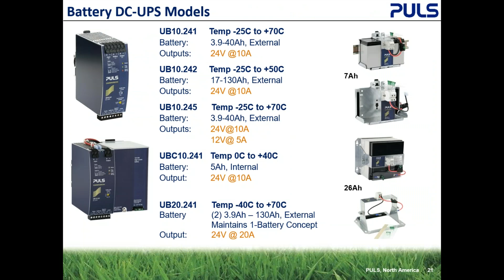I'm showing this because a lot of people now are getting into backup systems. I think they're starting to see the benefit of a DC backup. So we make DC backup systems, and I specify DC because everything Puls does is a DC output, we don't have any AC outputs. So if somebody says, I have a backup, but it's AC, it's an APC system, I just plug it in, let me tell you about an AC backup system. You're taking AC from the mains, converting AC to DC, charging a battery with that DC, and then going from the battery through an inverter, converting the DC back to AC. So it's very inefficient.